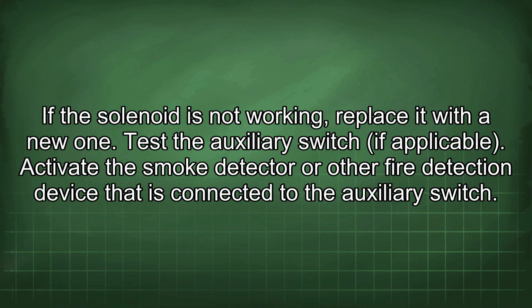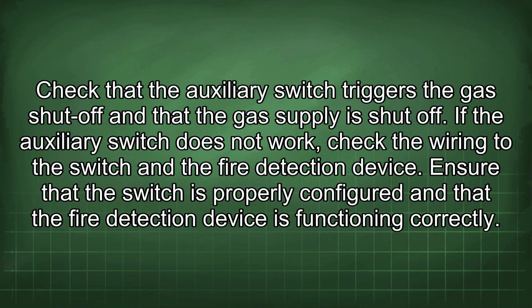Test the auxiliary switch if applicable. Activate the smoke detector or other fire detection device that is connected to the auxiliary switch. Check that the auxiliary switch triggers the gas shut-off and that the gas supply is shut off.